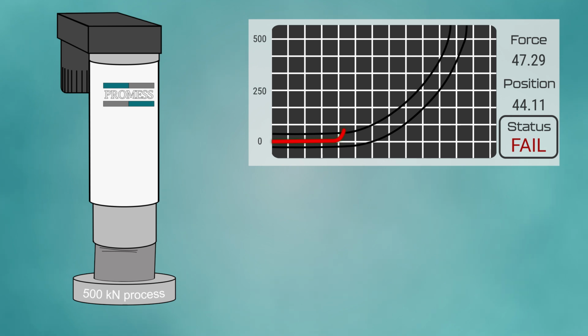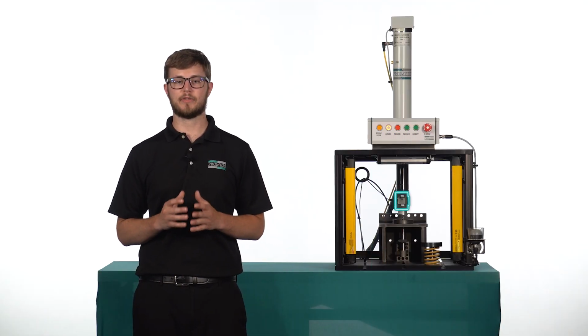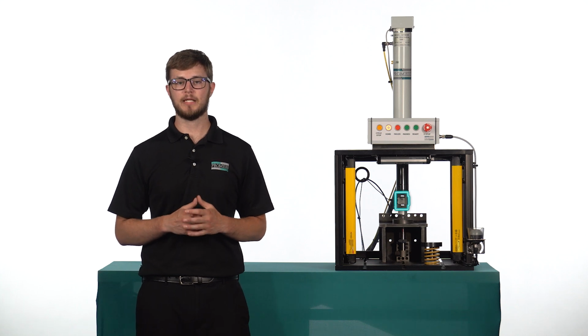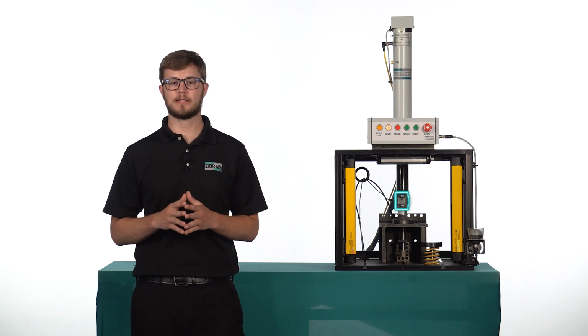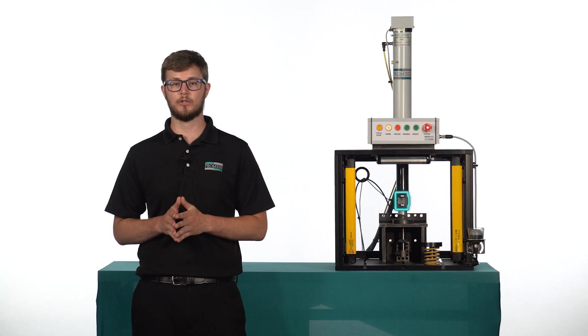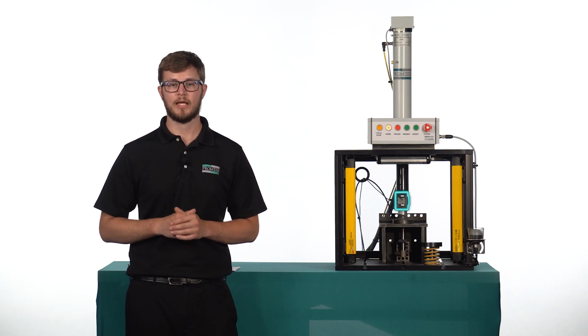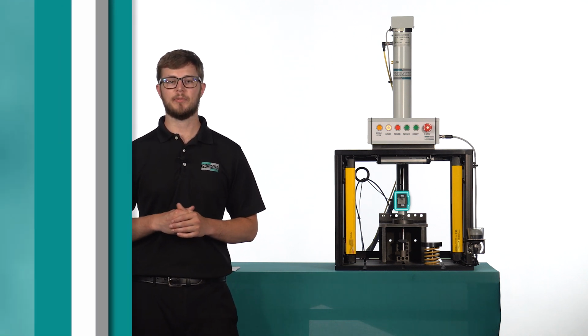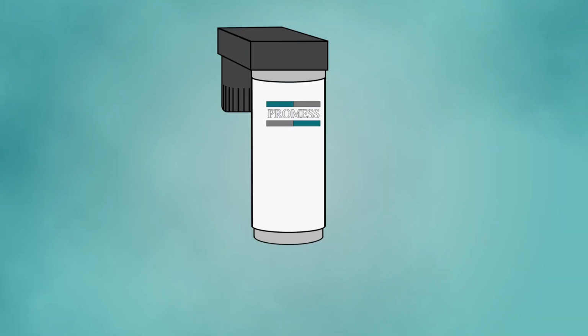With a 500 kilonewton, or 112,000 pound, press, it can be difficult to repeatedly detect a 100 pound, or 0.5 kilonewton, touch point. In this circumstance, it would be very beneficial to use a more precise 30 kilonewton external load cell.